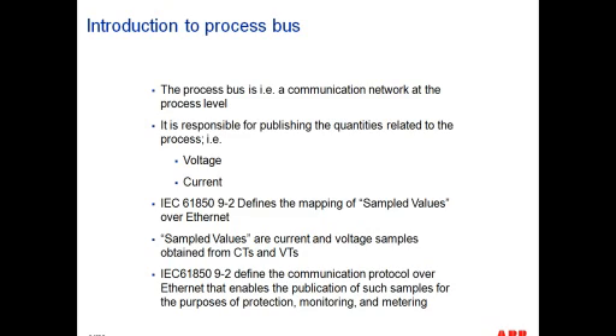And when we talk about sampled values, we're referring to current and voltage samples obtained from CTs and VTs, whether they're conventional or non-conventional. And we'll talk a little bit about that later on in the presentation. And IEC 61850 defines the communication protocol over Ethernet that enables the publication of such samples for the purposes of protection, monitoring, and metering. In the case of protection, monitoring versus metering, there are some slight differences that we'll touch on when we talk about power quality type applications.